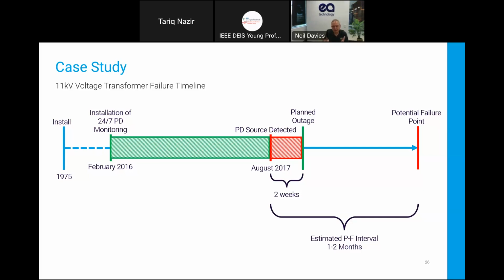So that's where you might get the instance, and you do come across it, where companies will say, well, I've had a failure. I look back at my old test results and we saw that we tested it 6 months ago. We had no evidence of PD. So why has it failed now? And what tends to happen at that point is you get one of two reactions. One is they'll blame the person who was testing whether they did it properly, or they will put into disrepute the effectiveness of doing testing in the first place, or any condition monitoring, realistically.